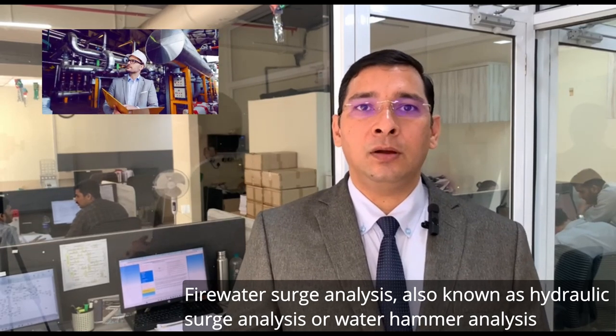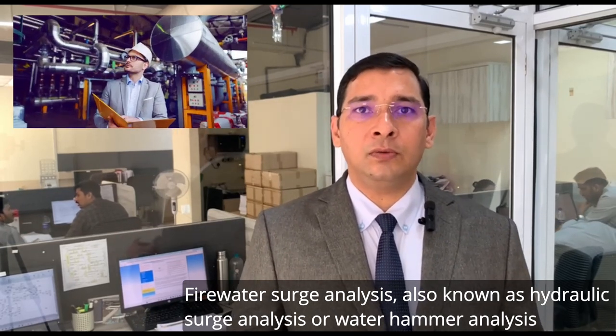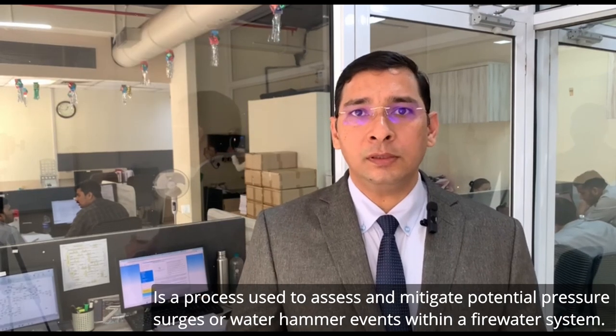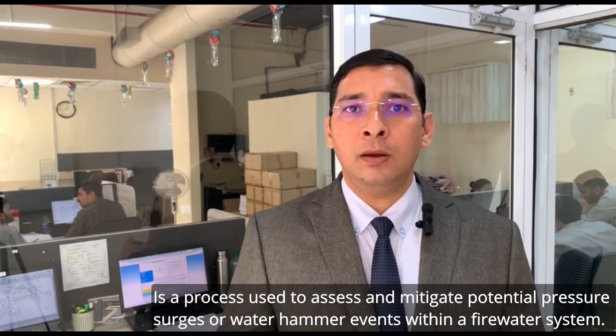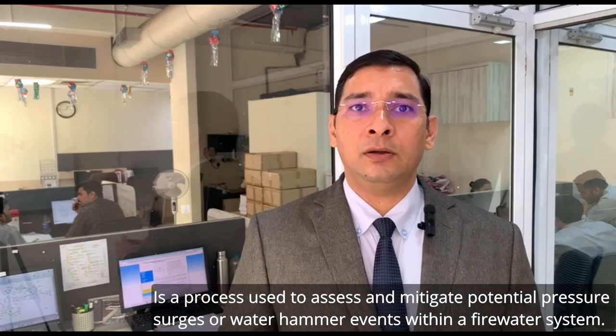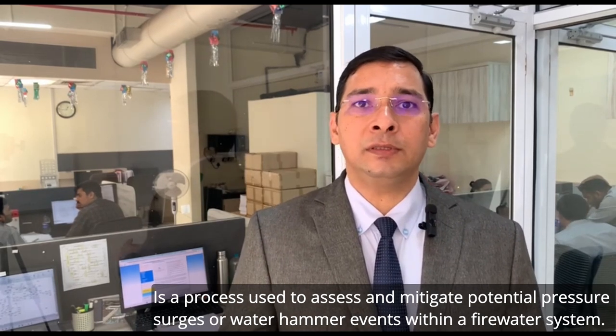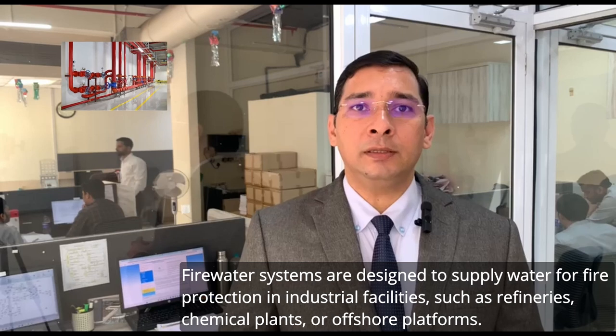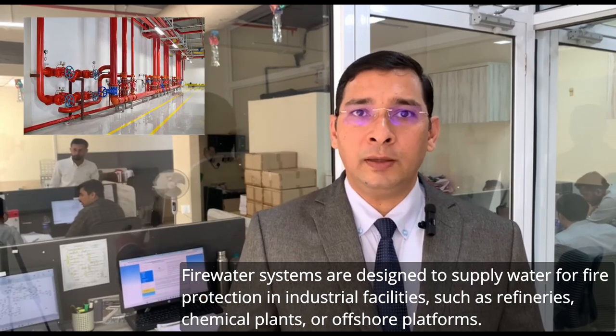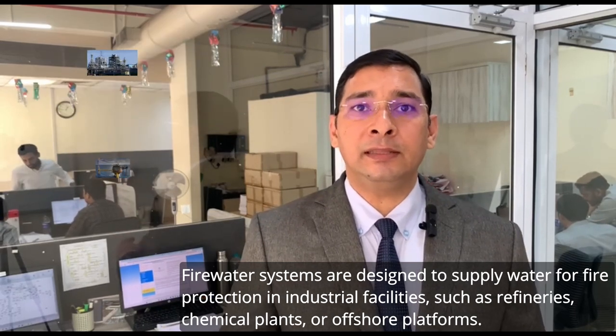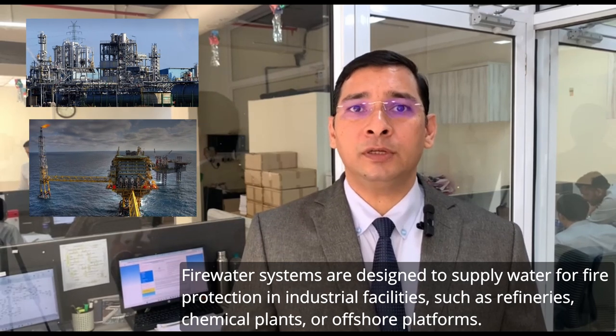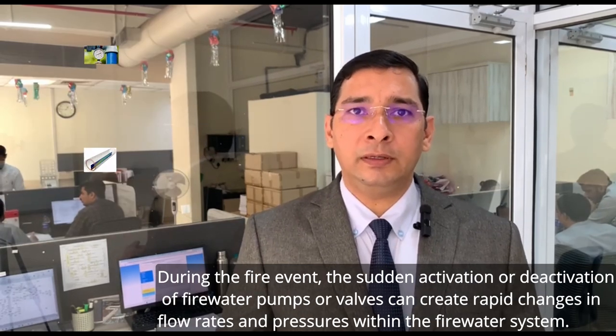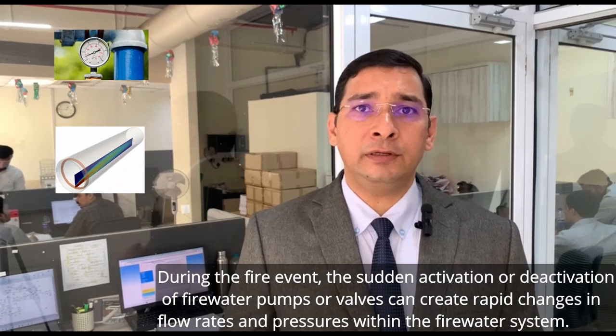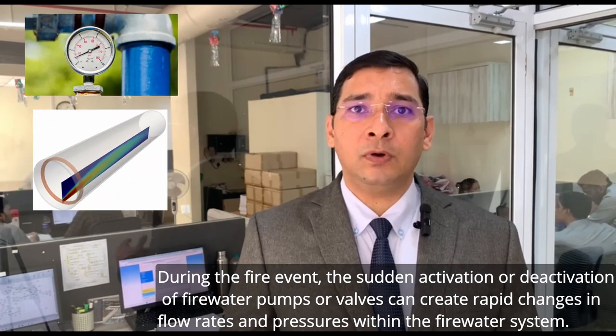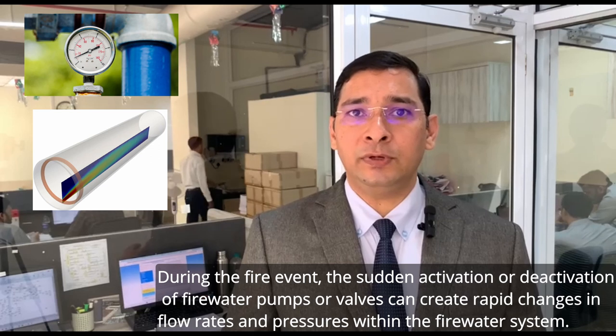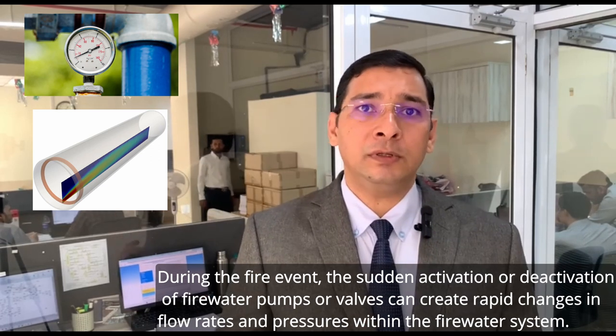Firewater surge analysis, also known as hydraulic surge analysis or water hammer analysis, is a process used to assess and mitigate potential pressure surges or water hammer events within a firewater system. Firewater systems are designed to supply water for fire protection in industrial facilities such as refineries, chemical plants, or offshore platforms. During the fire event, the sudden activation or deactivation of firewater pumps or valves can create rapid changes in flow rates and pressure within the firewater system.